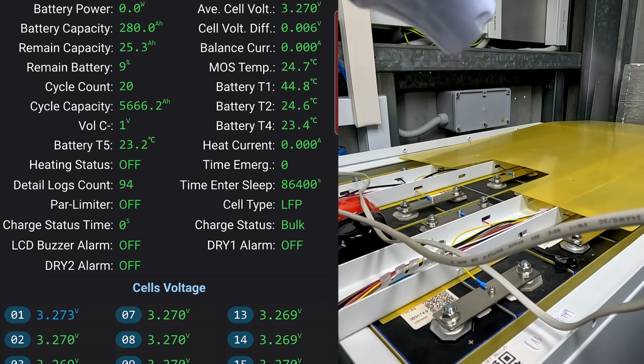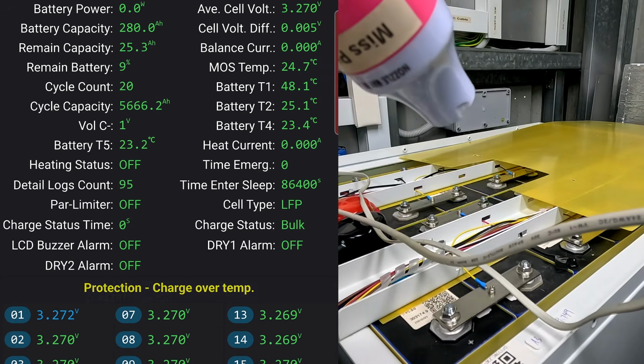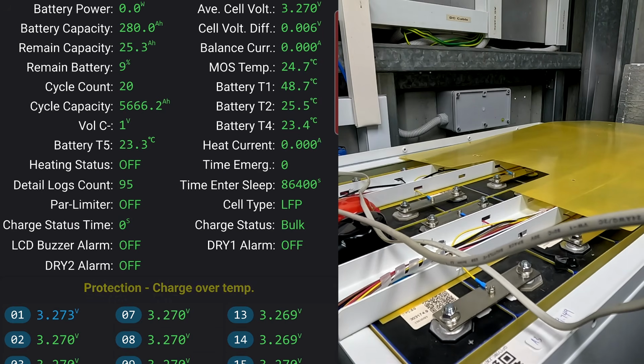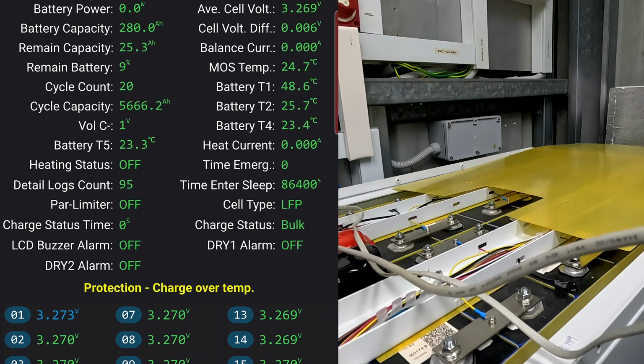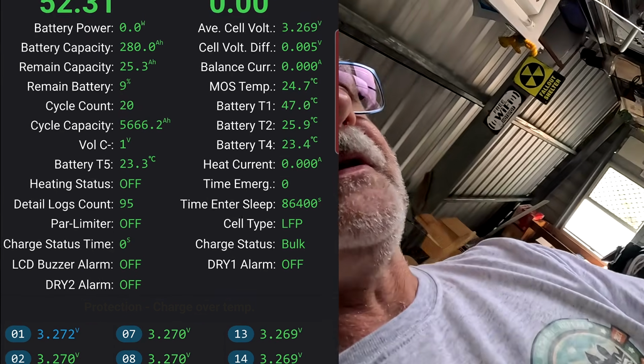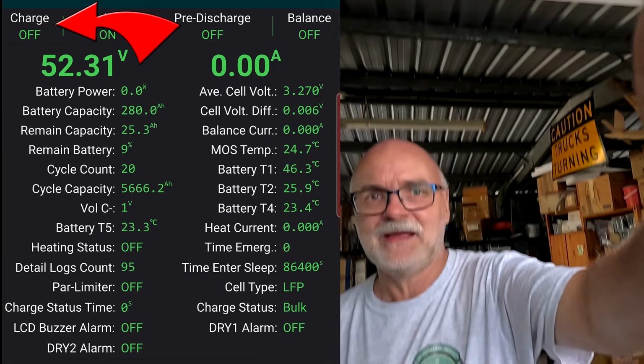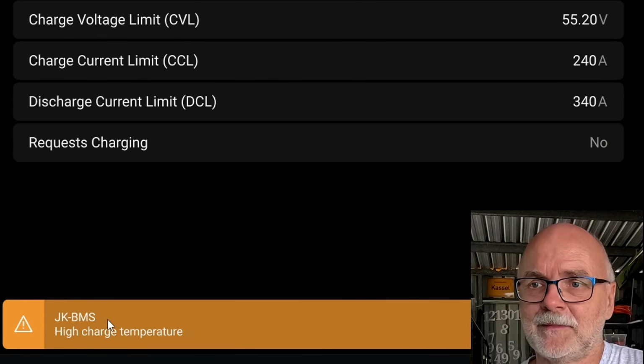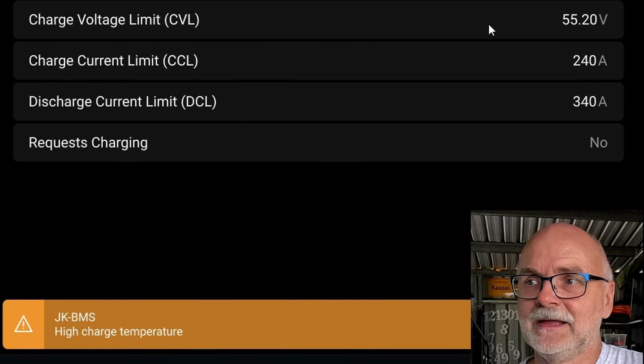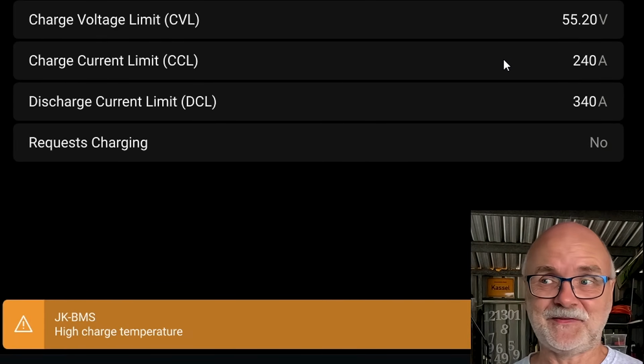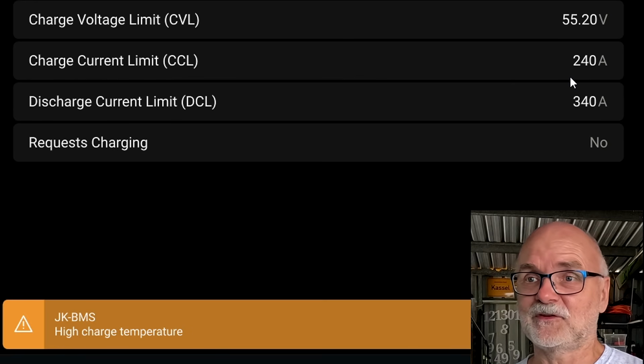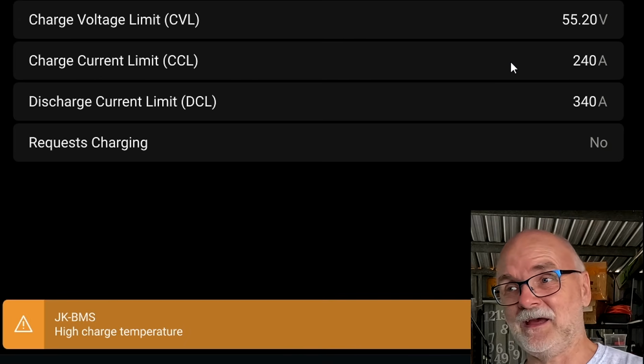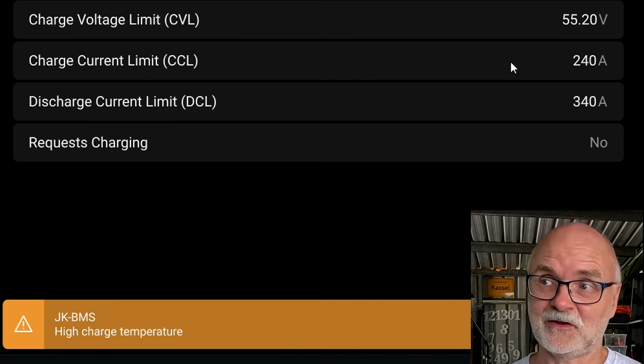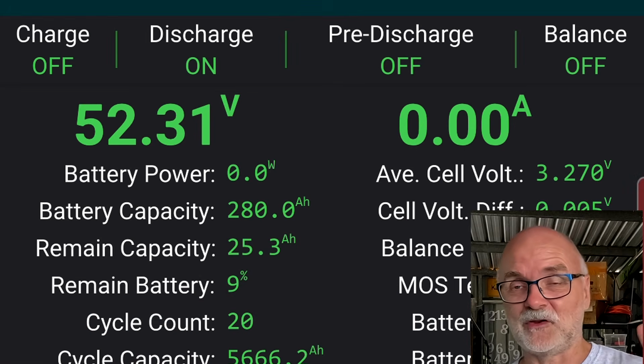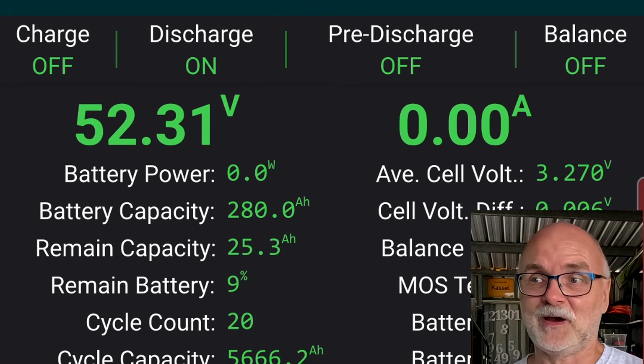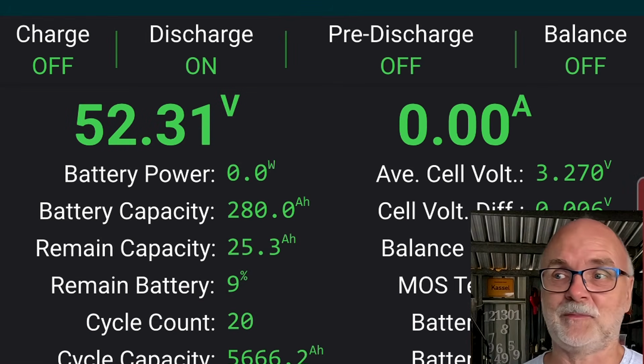There is protection charge over temperature protection alarm, whatever it's called. You can see the charge MOSFETs have turned off again. And here in the Victron we can see the JK-BMS high charge temperature. Again, one BMS is missing in the list of 4, so we have reduced the charge current to only 240 amps from 320. Charge MOSFETs have turned off, so nothing is going into this battery anymore, but we are still able to discharge this battery, of course.